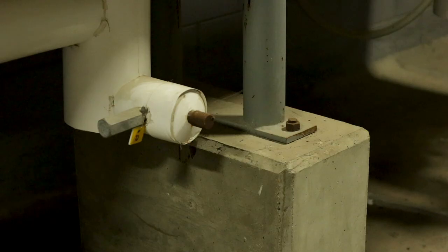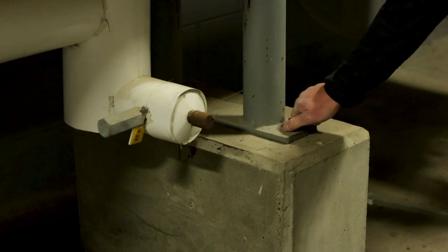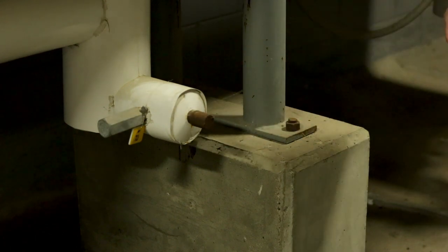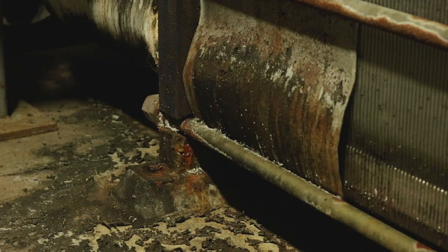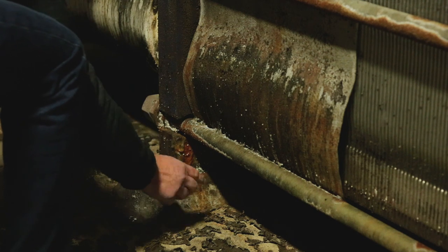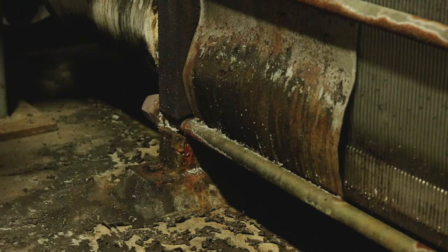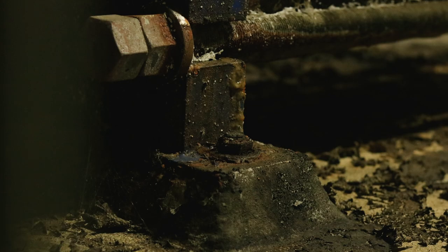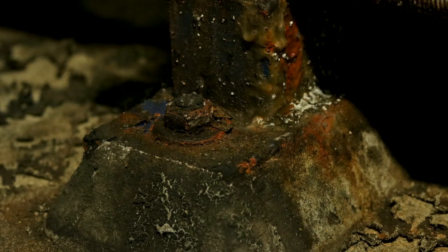Item D requires the inspector to verify that supports and anchorage are adequate. For a ground-mounted heat exchanger, the anchorage should be inspected to ensure that nuts are tight and free from corrosion. IIAR 6 has a separate piping checklist, so the focus of this question is not on pipe supports. This plate and frame heat exchanger anchorage has an unacceptable level of corrosion that must be addressed.